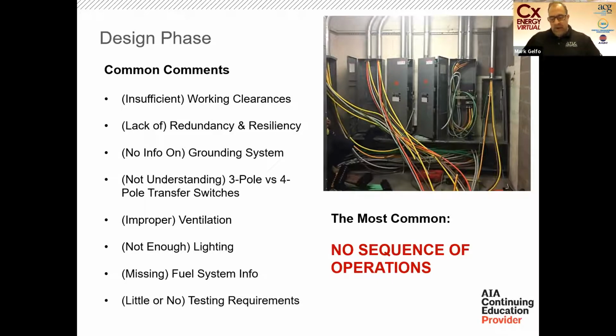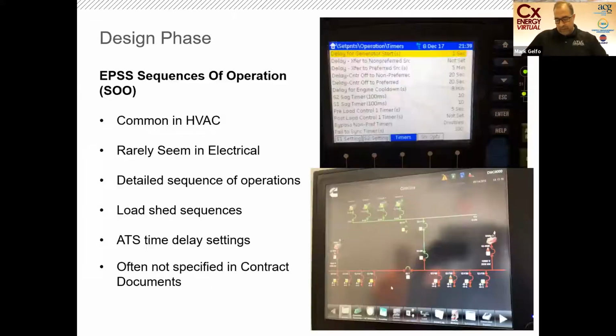Usually it has to do with working clearances, redundancy issues, and grounding issues. Surprisingly, environmental characteristics of the rooms is an issue that doesn't get enough attention. Ventilation and lighting and things like that are very important but don't get attention. But the biggest one, the most common thing we see, has to do with sequence of operations, or the lack thereof.